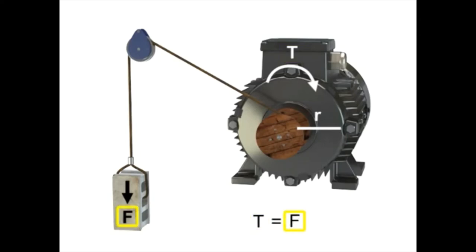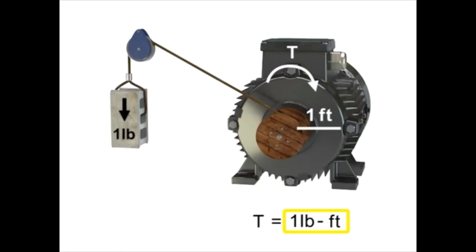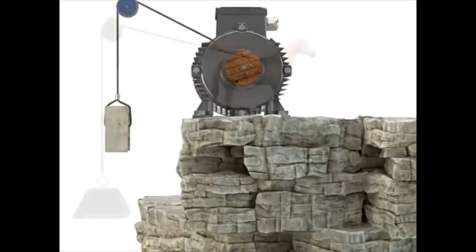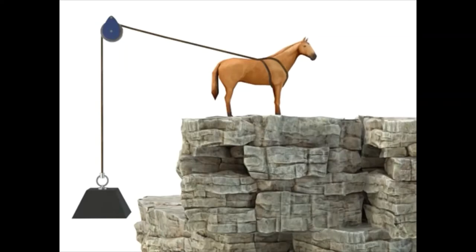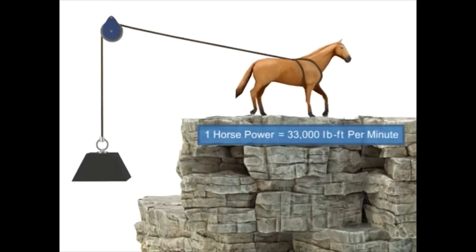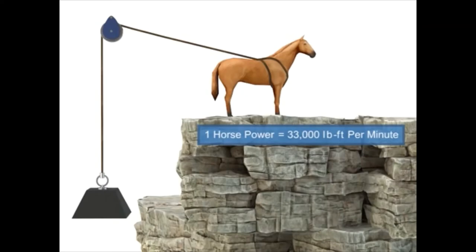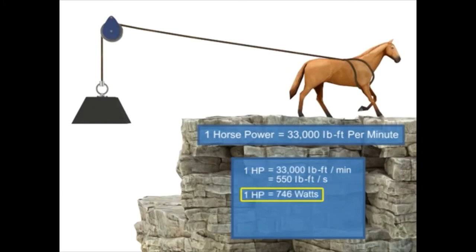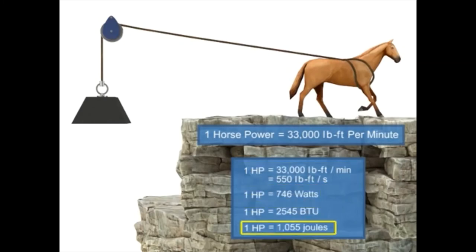Torque occurs when a force acts on a radius. Typical units of measurement for torque are pound-foot. The torque illustrated here is equal to one pound-foot. Horsepower is defined as the rate at which work is accomplished. Years ago, before motors were invented, most work was accomplished manually. It was estimated that one horse could accomplish approximately 33,000 pound-foot of work per minute, and thus the term horsepower was born. In modern terms, horsepower is simply another unit of measurement for power, and can be translated into watts, BTUs, joules, or any unit of power. Units that measure motor power are typically in horsepower or watts.